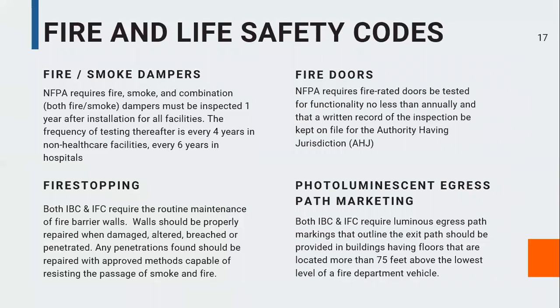Fire doors, NFPA requires the full code inspection for all fire-rated doors, and they must be tested for functionality no less than annually. And then a written record of that inspection must be kept on file for the authority having jurisdiction. Additionally, all repairs must be made after they are inspected and discovered. So fire stopping, so both the International Building Code and the International Fire Code require that routine maintenance of your fire barrier walls be maintained and be repaired when damaged or altered or breached or penetrated. Any penetrations found should be repaired and approved methods capable of resisting the passage of smoke and fire. And the requirement for this is they must be maintained at all times.